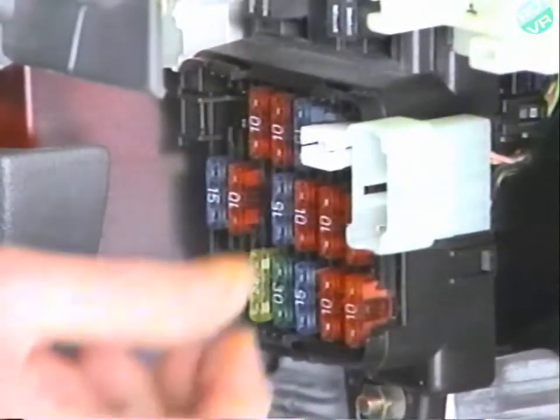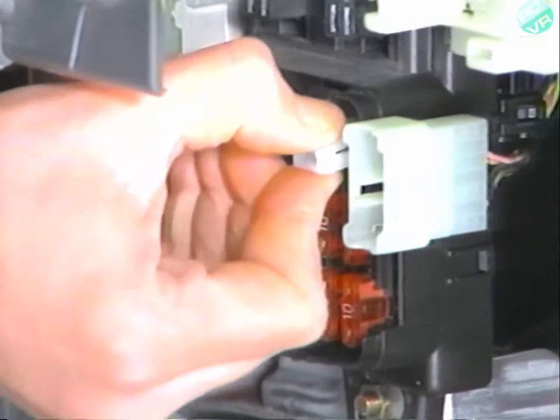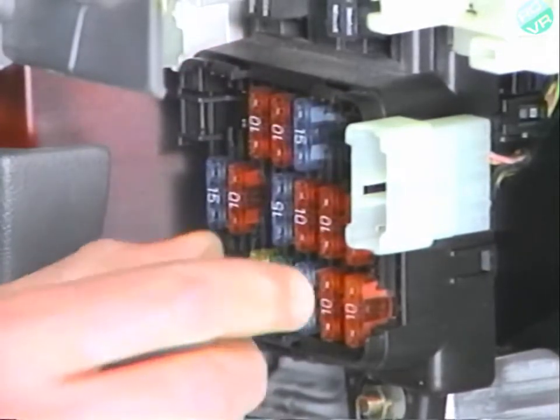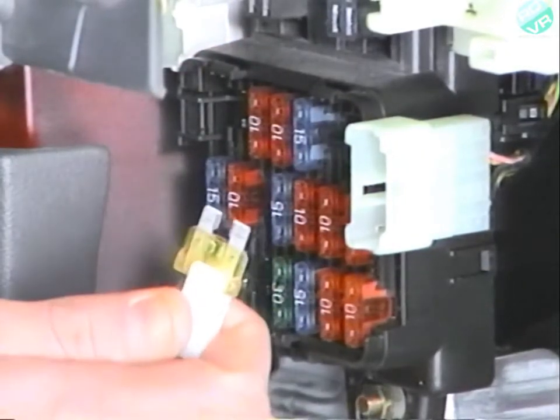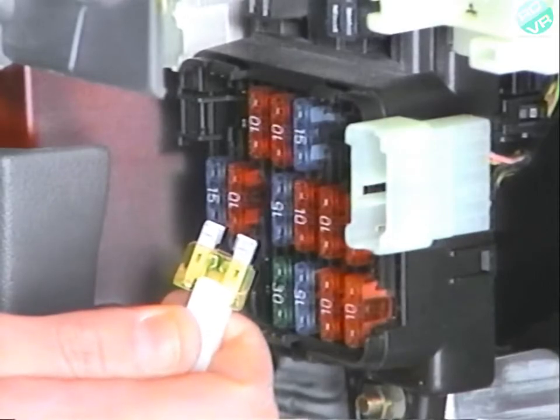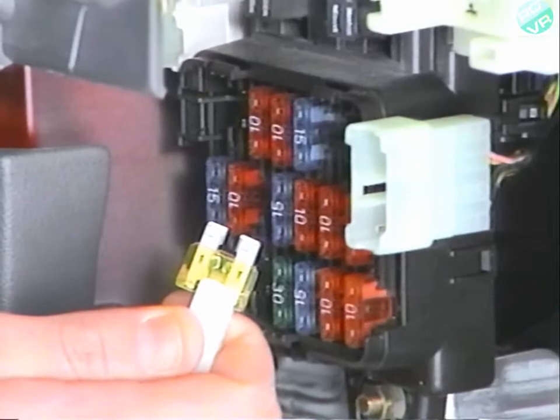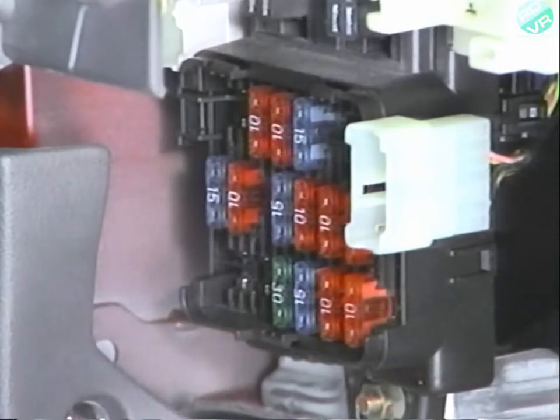Electrical trouble could also be caused by a faulty fuse. A common way to check a fuse is by removing it and visually inspecting it. A fuse with a melted center conductor is easy to detect, and the cause of the blown fuse should be determined. But the circuit through a fuse can also fail because of a poor connection at the fuse block.